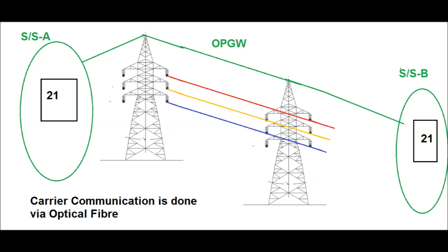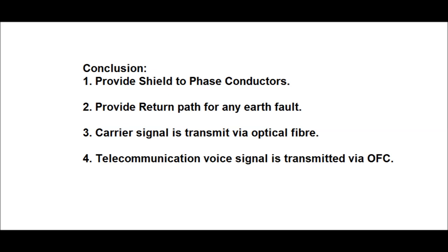If any fault occurs, it is sensed by the distance relay — that is, a Zone 1 carrier signal is sent from the distance relay. The analog signal is transformed to a digital signal via a digital protection coupler, and the same signal is transmitted via optical fiber to the remote substation. At the remote substation, the digital protection coupler again transforms the digital signal back to an analog signal, which is received by the distance relay located at the remote end. Thus carrier communication is done by optical fiber.